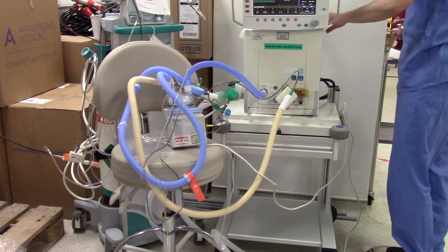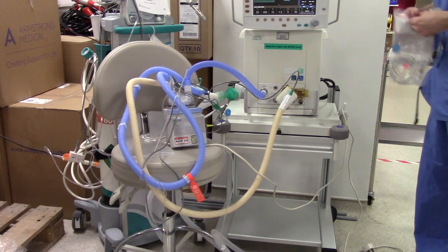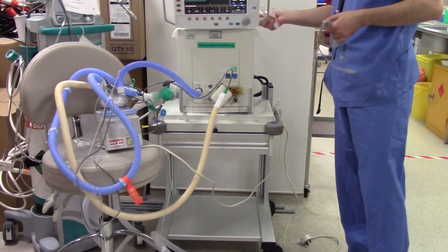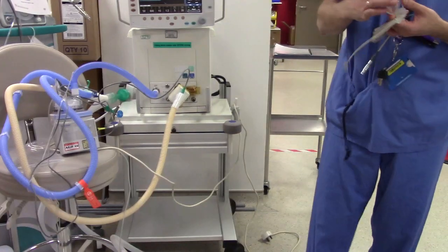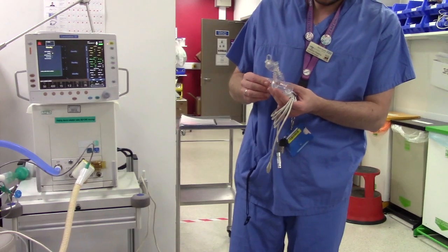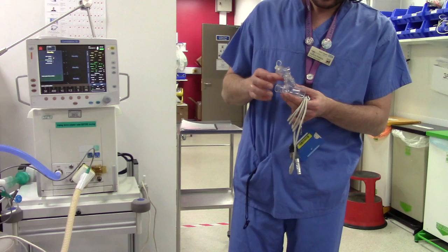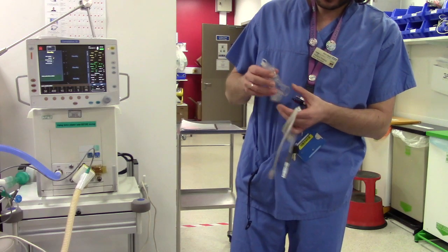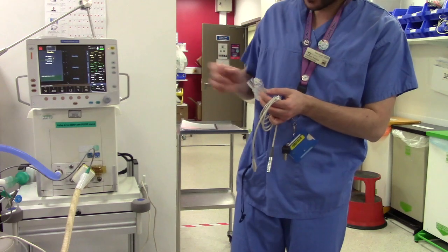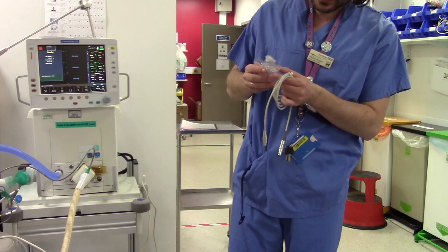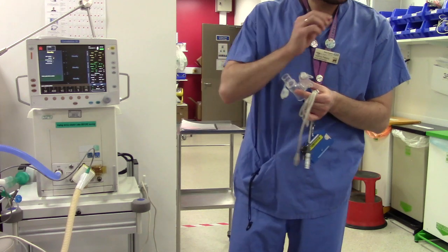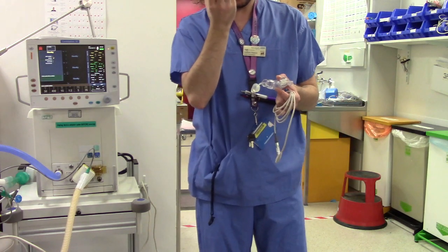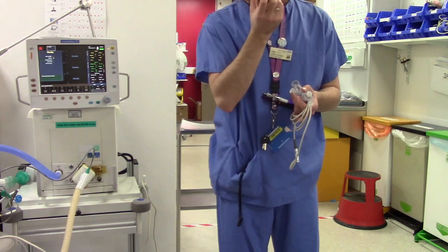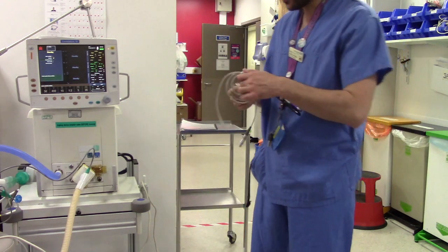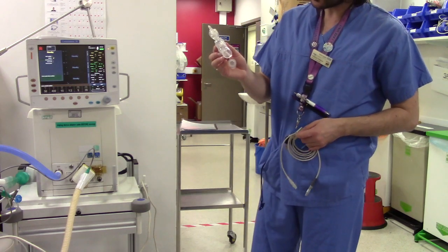Then I talked about the nebulizer. So this is the nebulizer I was talking about. As I said, you don't need to use any gas to drive it. This will be driven by the ventilator via a pump that's inside. It's like a micro pump, and it will create even smaller particles than the gas-driven nebulizer can create. So for that you need this part, which is called the nebulizer kit.